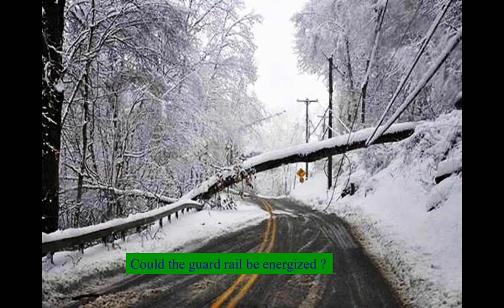Now that we talked about some things, maybe a couple of months ago you would have said, "Oh, what a quaint winter scene." But now let's look at this differently. Let's look at it from an electrical standpoint. Could the guardrail be energized? Well, I don't know. Look up there. All the three-phase primary got ripped down. That tree could be laying on some of that primary, and it looks like some of the primary is down there. That tree could be easily energized, and that tree is touching the guardrail. That guardrail could be energized to touch and step potential just through that contact right there.